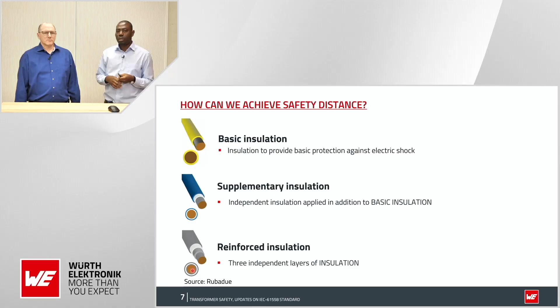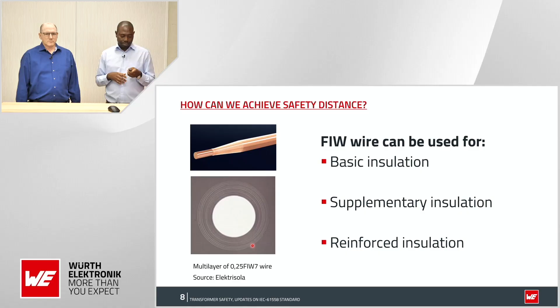According to 61558, you can also achieve safety using a specialized type of wire called fully insulated wire, shown here. This picture is from Elektrisola, a company that manufactures wires. It's based on copper with insulation layers realized with enamel, applied homogeneously so there are no pinholes in the insulation layer. Through this approach, you can achieve basic, supplementary, or reinforced insulation, and this wire can be used according to 61558 to achieve the levels of safety already presented.